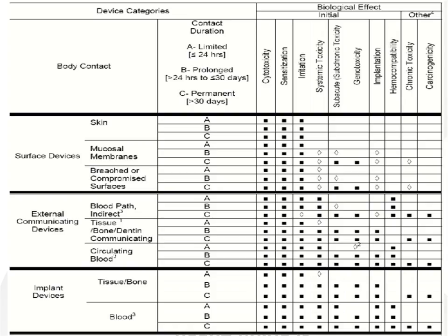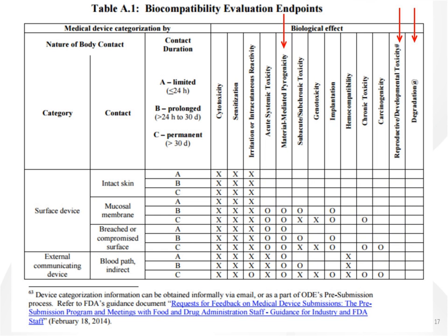And actually, when you look at risk, a lot of times those devices carry more of a risk than some metal device that sits in your body for the length of the lifetime. Because when you look at most devices' extractable profiles, the majority of those compounds get extracted out within the first 72 hours, and then it starts to taper off down into a small amount. So if your biggest impact is in that first 72 hours, 24 hours, whatever the device may be, and you're getting a new device every 24 hours, you're getting a brand new peak or dose of the highest peak over and over again, compared to something that may be lessening the amount of chemicals being exposed. So those are things you have to evaluate when you're looking at the risk of your device.